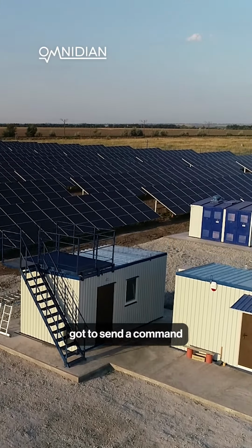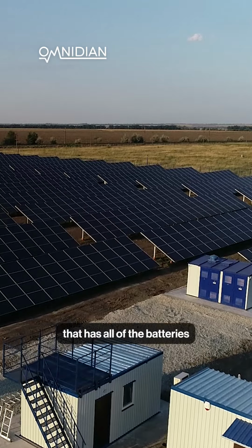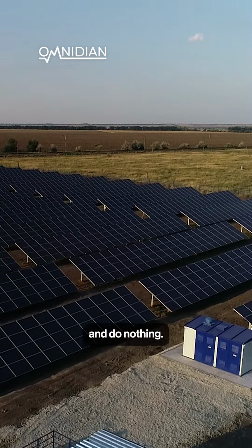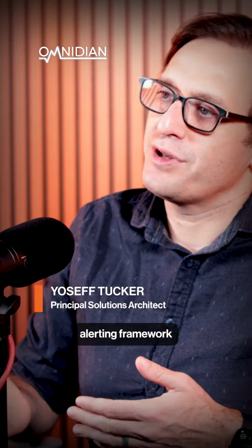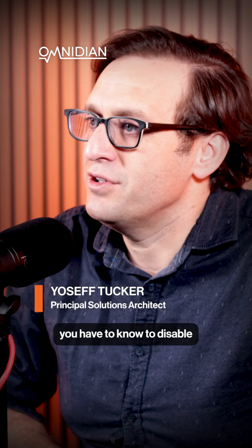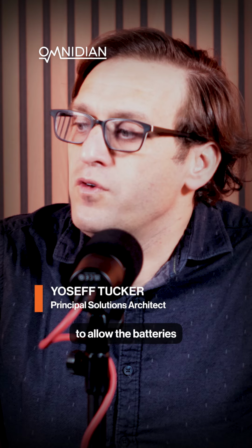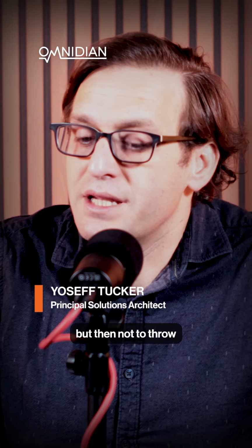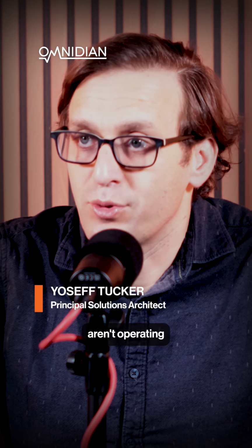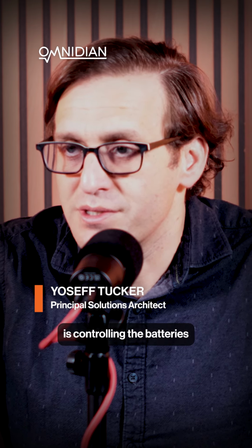So somebody's got to send a command that has all of the batteries charge up and sit there and do nothing. If you have an alerting framework that is responsible for detecting when the batteries are doing nothing, you have to know to disable that alerting framework to allow the batteries to charge, but then not to throw a bunch of false positive alerts saying that the batteries aren't operating because somebody else is controlling the batteries and they're in a different state. So there's a degree of complication associated with at least monitoring the performance of the battery.